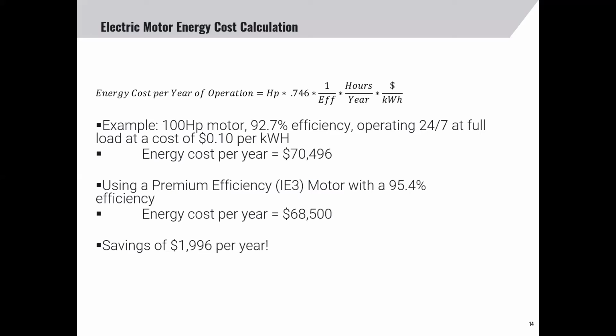Maintenance costs for the first year are pretty minimal. Basically, you would have the cost to grease the motor, and depending on the manual, it could be 2 to 3 times a year. But over a 10-year life, I would expect that you would have to replace the bearings maybe once or twice. You might even have to rewind the motor. And even with those expected maintenance costs, those costs are only going to represent 1% of the cost of ownership. You can expect to have an electrical consumption cost of well over $600,000 to operate that motor. Go to the next slide, please.